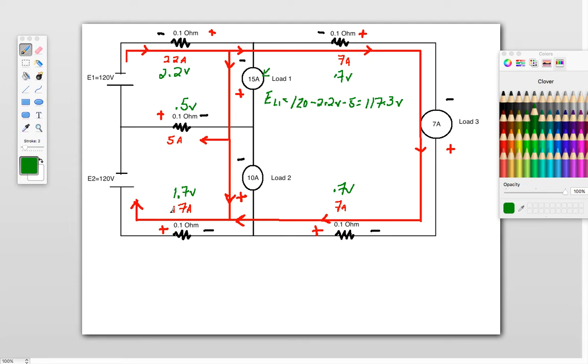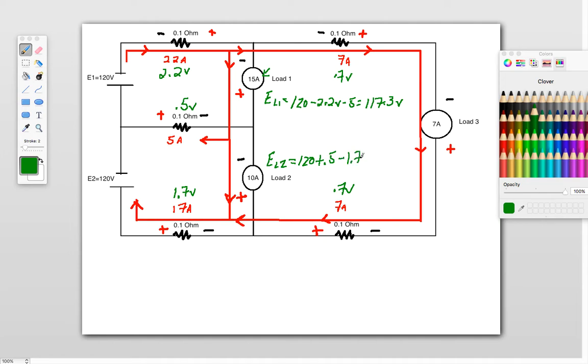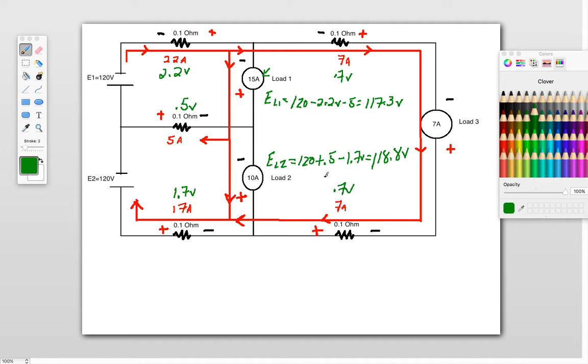Now, if we apply the same rules here, we look at this, my voltage at load 2 is going to be equal to 120 volts. Follow the current direction, don't worry about this is going in this direction, we know that's coming home here. So we're going to follow in this direction here. And the first sign we come to is a positive. So we're going to say, 120 plus 0.5, and we get to here, we get through here, we get a negative, so it's 120 plus 0.5 minus the 1.7 volts, which gives me 118.8 volts. So E2 is 118.8 volts, 120 plus 0.5 minus 1.7, 18.8 volts. Now we do load 3, and we do the same thing.